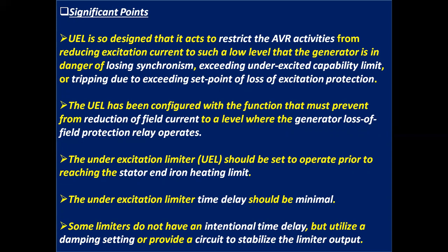The under excitation limiter has been configured with the function that must prevent reduction of field current to a level where the generator loss of field protection relay operates.